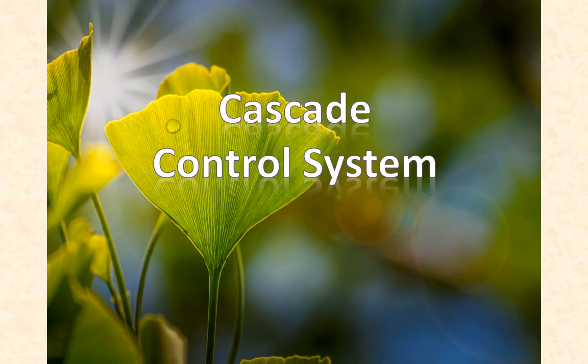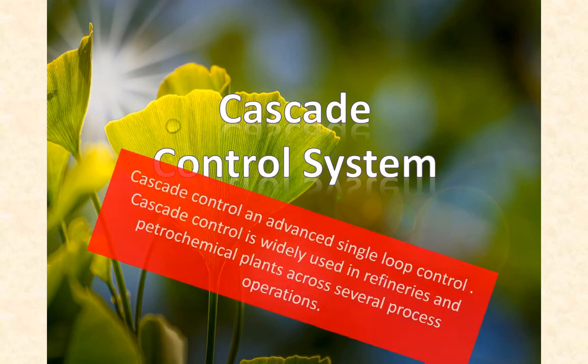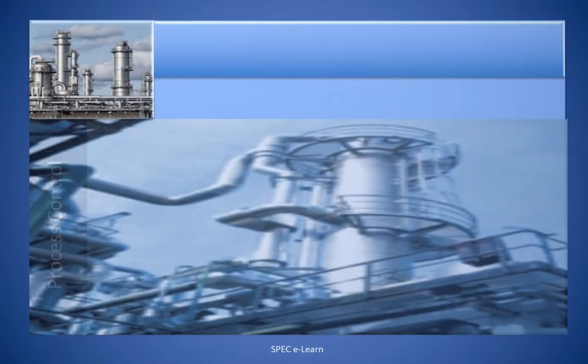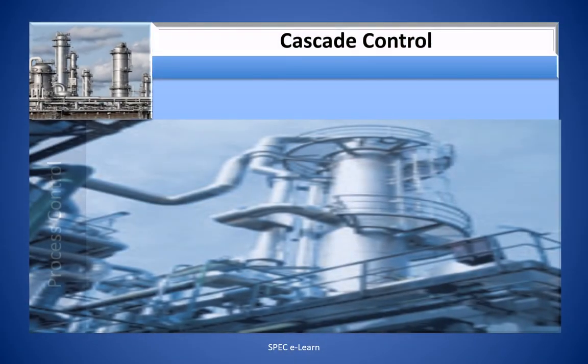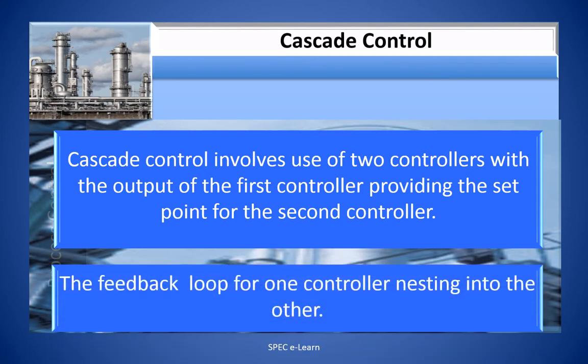Having discussed split range control, we will move on to cascade control. What is cascade control and how is it different from other closed loop control? Cascade control is an advanced single loop control, widely used in refineries and petrochemical plants. It involves use of two controllers, with the output of the first controller providing the set point for the second controller, with the feedback loop for one controller nesting into the other.